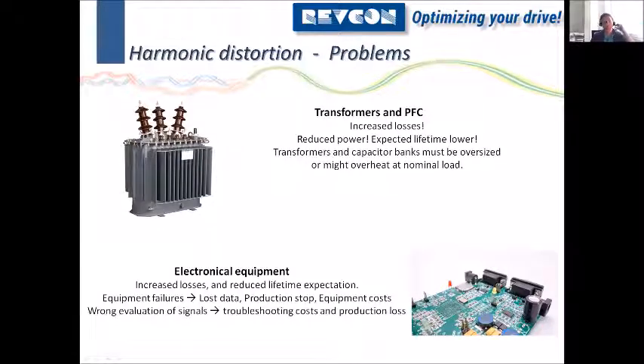And another one is the reduced lifetime of electronic equipment. Looking at electronic equipment, all of it has some kind of input rectifier and some kind of capacitor in the front, because they are DC supplied somewhere internally. So this capacitor will see the full DC bus ripple of the voltage if we have higher harmonics. So it's typically not immediate damage. It's more a damage that will harm your equipment over time. So if you see your PCs or computers or whatever electronic equipment you have dying after 12 months, after 6 months, it's not always due to bad quality. It can be the power quality that just makes your equipment suffer.